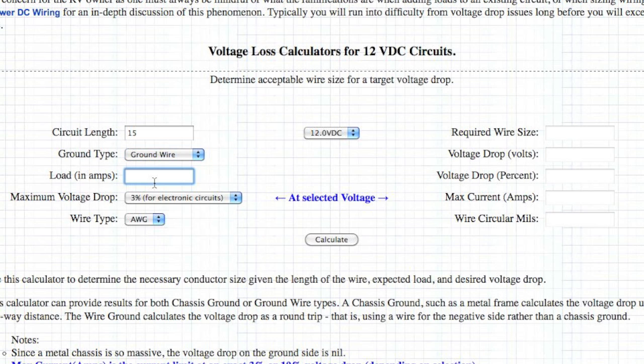The load is 4 amps, and the maximum voltage drop, we have a choice of either 3% for electronic circuits or 10% for electrical circuits. Now, this recommendation comes from the U.S. Coast Guard in the regulation 33 CFR 183, which states that they want to see no more than a 3% voltage drop for sensitive electronic circuits, yet general purpose electrical circuits can use a 10% voltage drop.